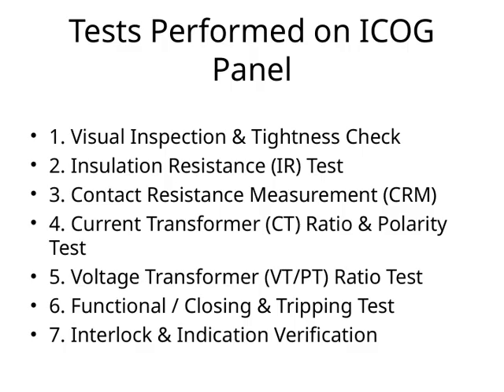This test simulates real operating conditions to confirm that the panel's protective and control functions are working properly, ensuring the system responds correctly during faults or operational commands. Finally, we carry out the interlock and indication verification. This step is essential to confirm that all safety interlocks are correctly configured and that the indicator lights and alarms are functioning, helping prevent unsafe conditions and ensuring proper system operation. Together, these tests form a comprehensive approach to validating the ICOG panel's performance, safety, and reliability, which are all critical components in maintaining a secure and efficient power system.